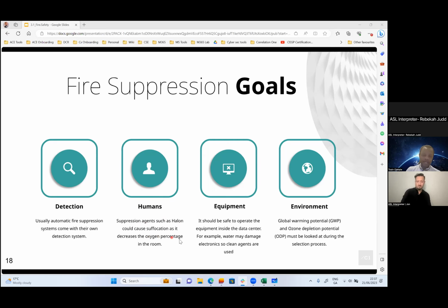The responses are spot on - oxygen, yes absolutely. So the next one is equipment: it should be safe to operate the equipment inside the data center. For example, water may damage electronics, so clean agents are used. Remember I mentioned this when someone asked whether we need to switch off the servers when there's a fire disaster. So if the fire is within the data center itself, where you have your servers and racks, a clean agent is mostly used within the rack space because you don't want to use water. If you use water, there's a chance you damage the server.